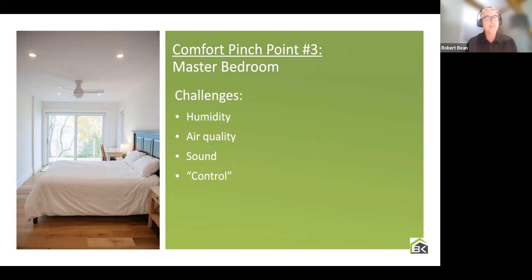So humidity, let's start with that. You talk about two people in a space, likely an attached bathroom and shower, there's a huge source right there. So you have to talk about really effective bathroom exhaust systems. We tend to use more variable speed systems with high capacities. Some of these bathrooms had 250 CFM exhaust. People might get shocked about that, but you're not running them at 250 unless you need it, to purge a space quickly.